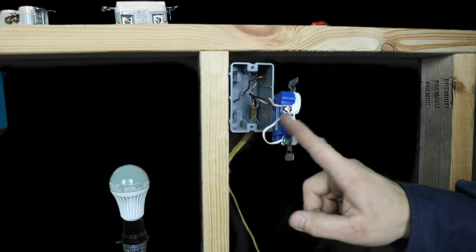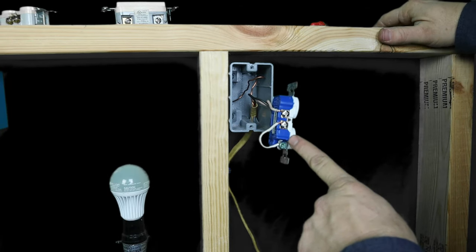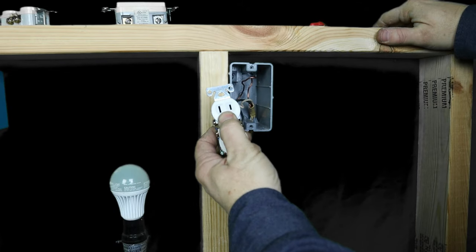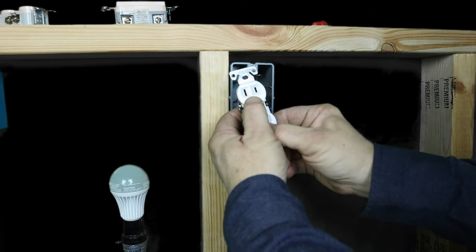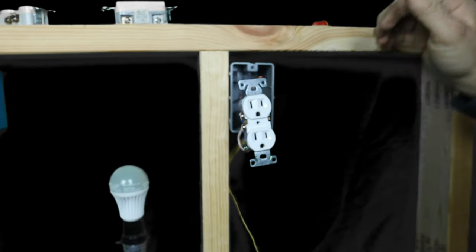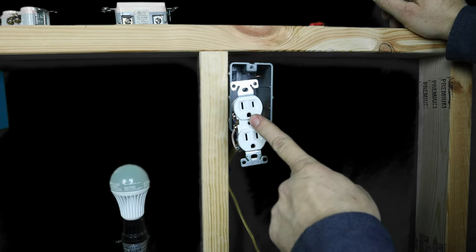The way to correctly fix this is to put a GFI in here, or another two-prong receptacle would look just like this with no grounds. You can put that back just as easy as you could, but you cannot, you cannot do this.